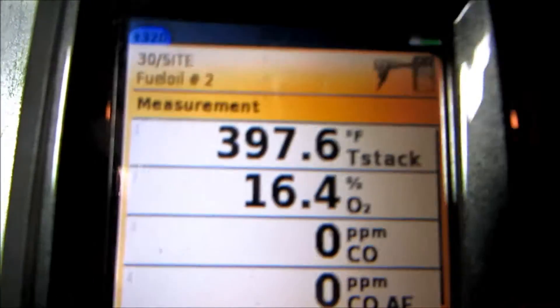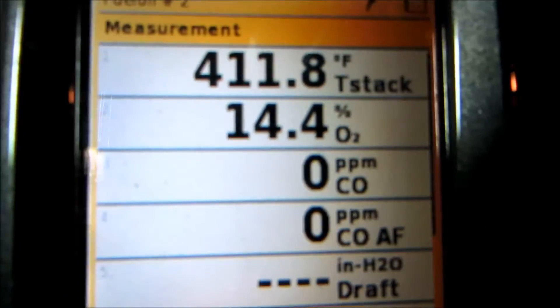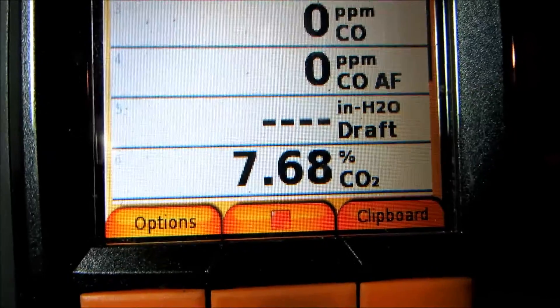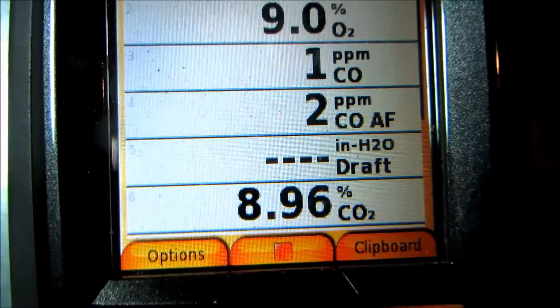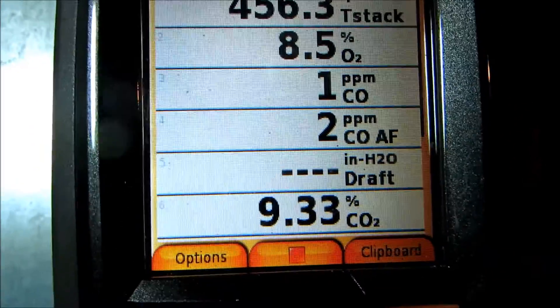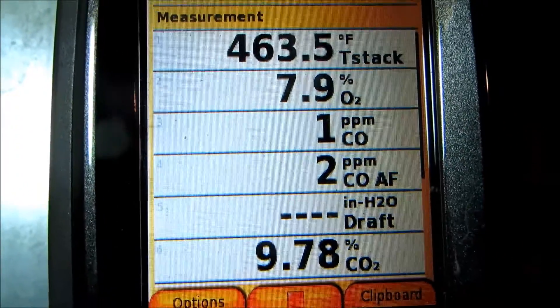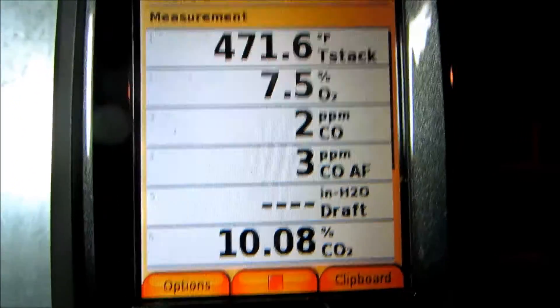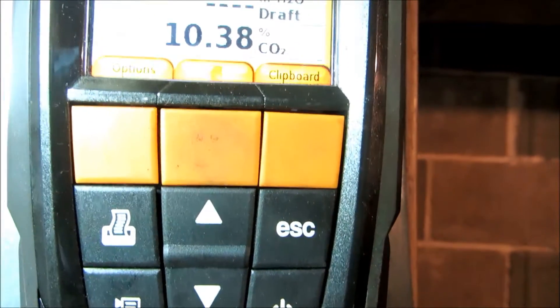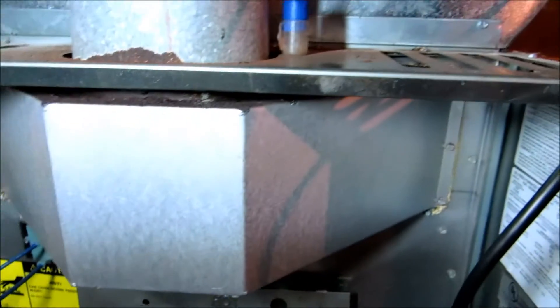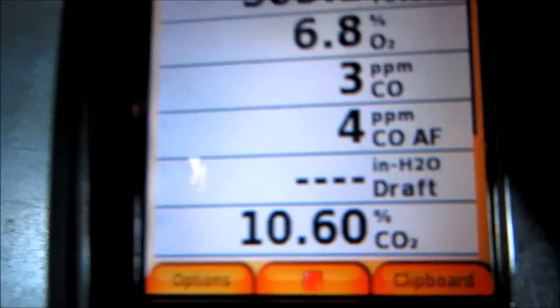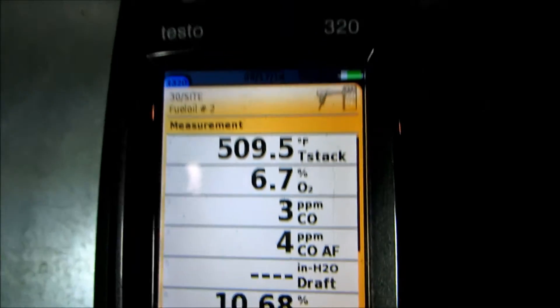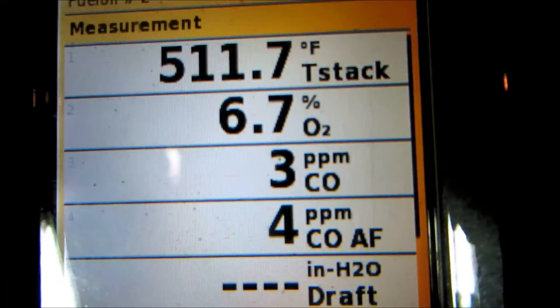We're looking at the parts per million right there - that's the CO I'm really concerned about, and also the oxygen and CO2. CO2 wants to be around 12, just below 12, somewhere in that range is good. On a furnace like this, I like to run this thing lean because the heat exchanger is extremely hard to clean, it's all a bunch of tubes. So I'm running it a little bit on the lean side.